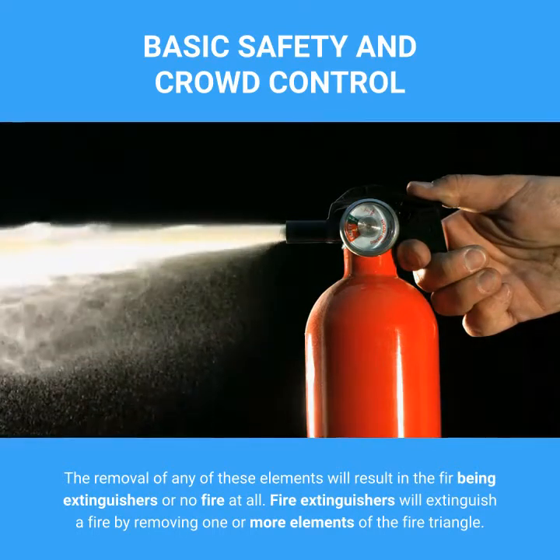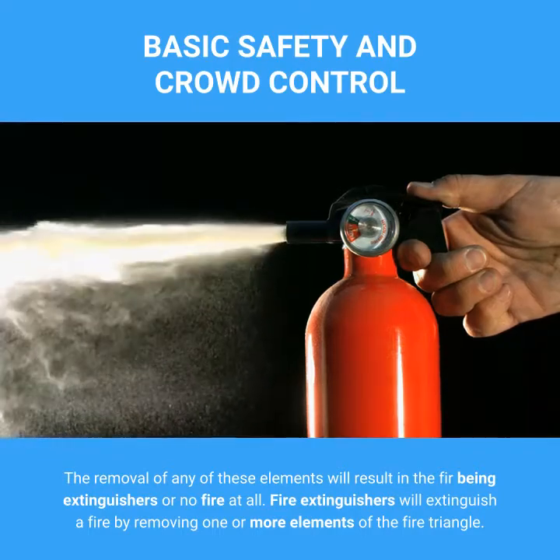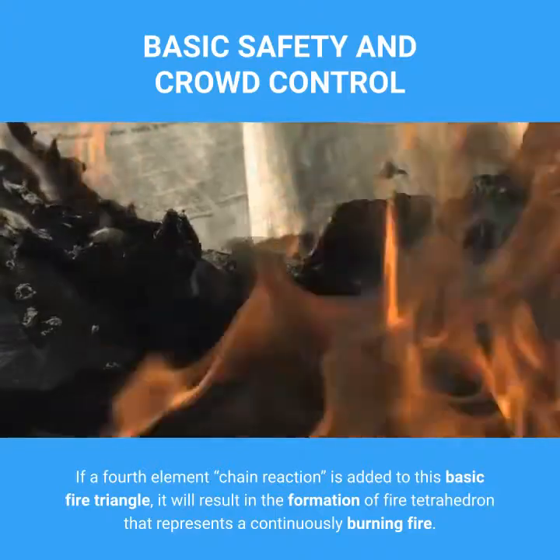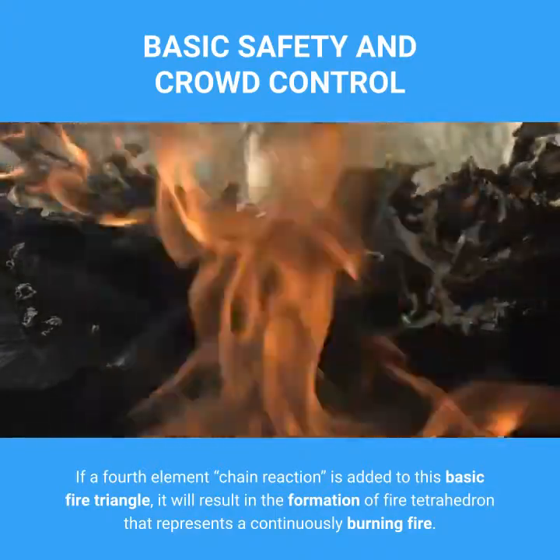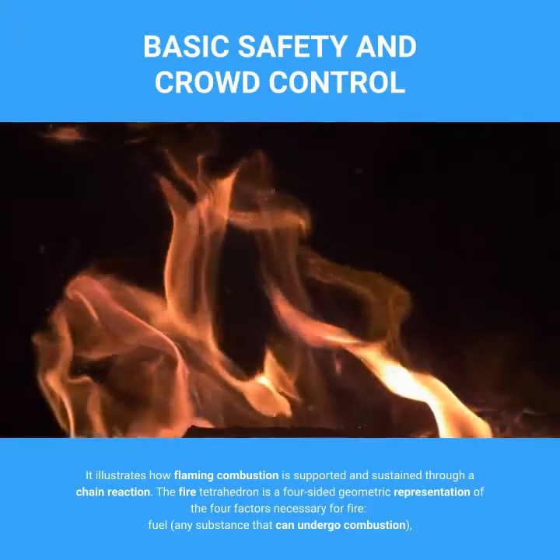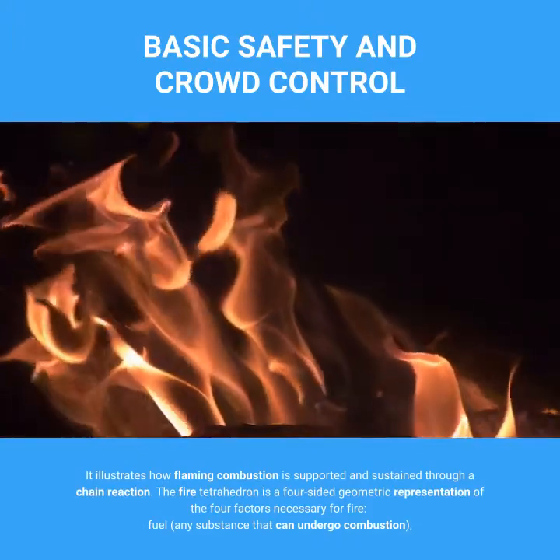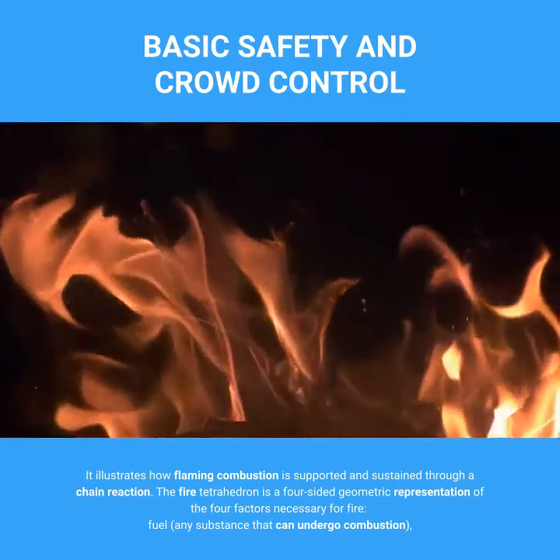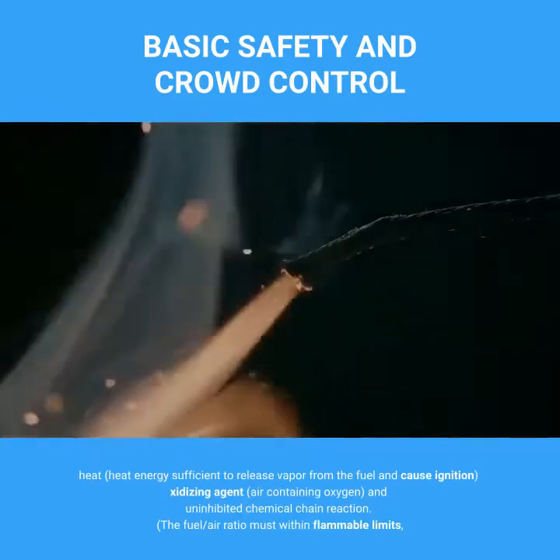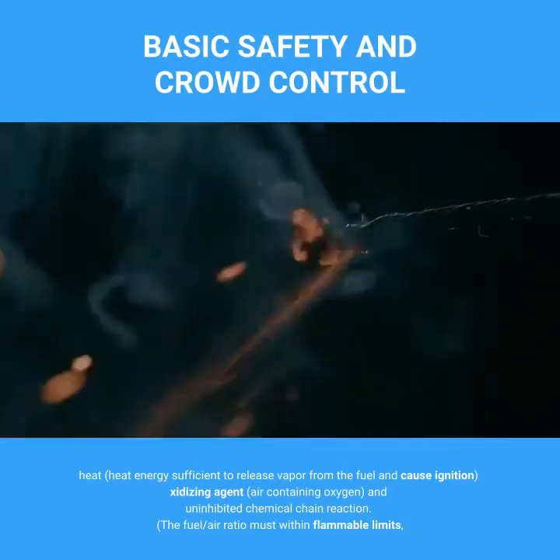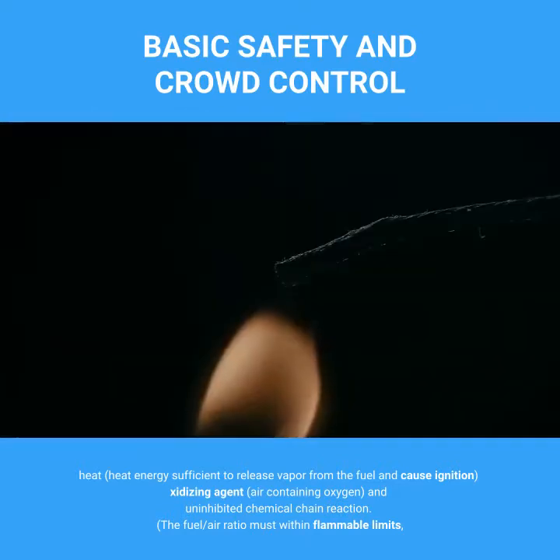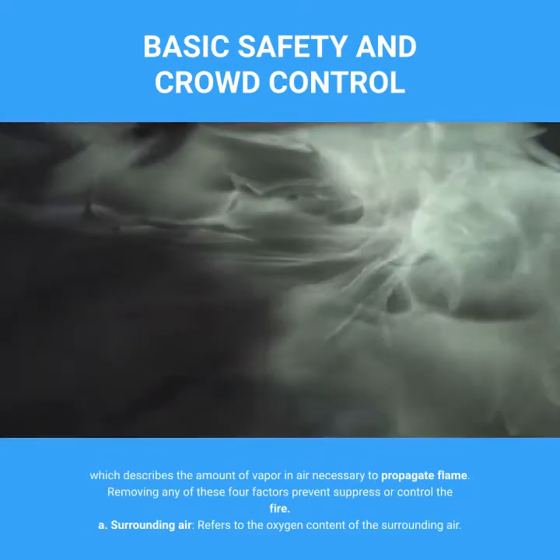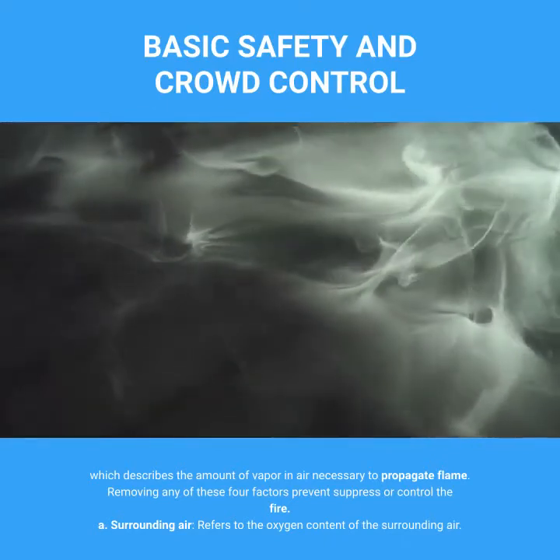Fire extinguishers will extinguish a fire by removing one or more elements of the fire triangle. If a fourth element — chain reaction — is added to this basic fire triangle, it results in the formation of a fire tetrahedron that represents a continuously burning fire. It illustrates how flaming combustion is supported and sustained through a chain reaction. The fire tetrahedron is a four-sided geometric representation of the four factors necessary for fire: fuel, heat, oxidizing agent (air containing oxygen), and uninhibited chemical chain reaction. The fuel-air ratio must be within flammable limits, which describes the amount of vapor in air necessary to propagate flame. Removing any of these four factors prevents, suppresses, or controls the fire.